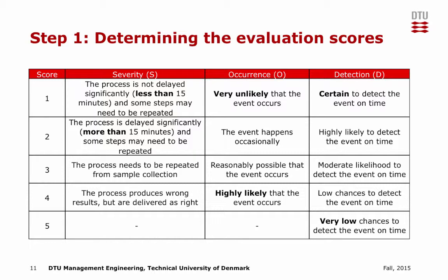In this example, a 4-grade scale has been defined for severity and occurrence, and a 5-grade scale for detection. For severity: a score of 1 if the process is not delayed significantly — less than 15 minutes — and some steps may need to be repeated; a score of 2 if the process is delayed significantly — more than 15 minutes; a score of 3 if the process needs to be repeated entirely; and a score of 4 if the process produces wrong results that are delivered as correct. For occurrence, a score of 1 means it is very unlikely the event occurs, and a score of 4 means it is highly likely. For detection, a score of 1 means the event is certain to be detected on time, and a score of 5 means there are very low chances of detecting the event on time.